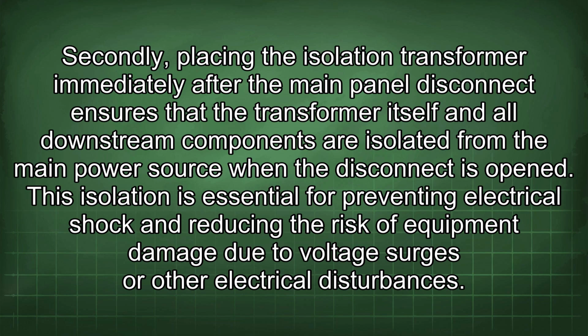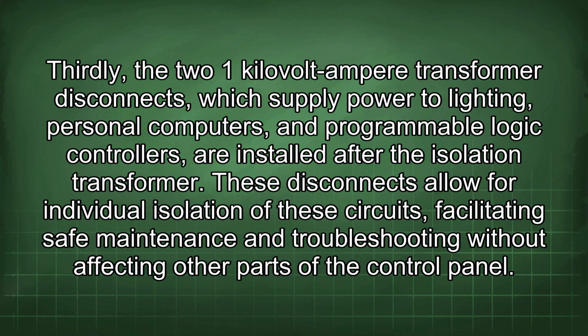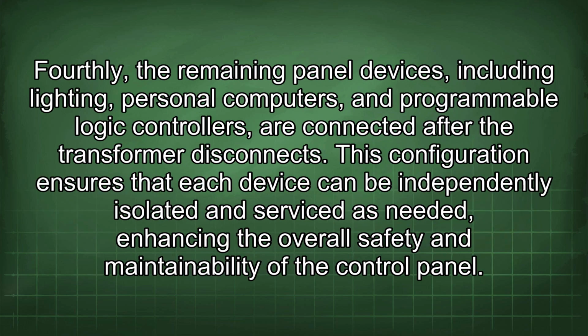Thirdly, the two 1 kVA transformer disconnects, which supply power to lighting, personal computers, and programmable logic controllers, are installed after the isolation transformer. These disconnects allow for individual isolation of these circuits, facilitating safe maintenance and troubleshooting without affecting other parts of the control panel. Fourthly, the remaining panel devices, including lighting, personal computers, and programmable logic controllers, are connected after the transformer disconnects. This configuration ensures that each device can be independently isolated and serviced as needed, enhancing the overall safety and maintainability of the control panel.